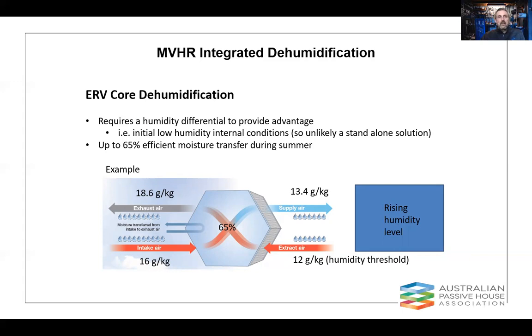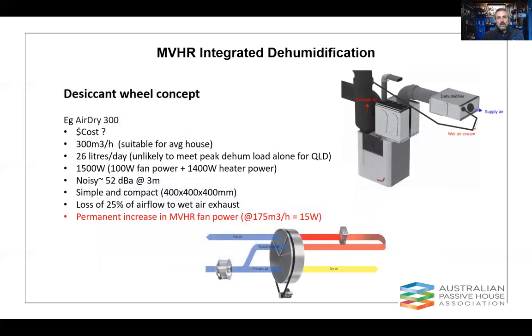So as we've touched on, ERV cores aren't a standalone solution. They're going to need some dehumidification as well. We're going to talk about a couple of different concepts here for this dehumidification. So the first is the desiccant wheel concept. So as it sounds, it's a rotating wheel, and it's actually got some coatings on the wheel that absorb moisture out of the air. Now the concept here is we pass air through the wheel, we absorb the moisture, and then it rotates into a little sector that you can see there.